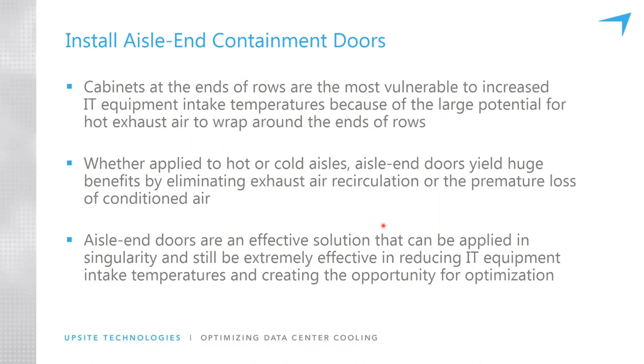Even on cold aisle containment, if there's not hot air problems, if there's not hot spots in the cold aisle, the doors may be very beneficial still, because what they do is they contain the cold air in the aisle and keep it from leaving prematurely and flowing back to a cooling unit.